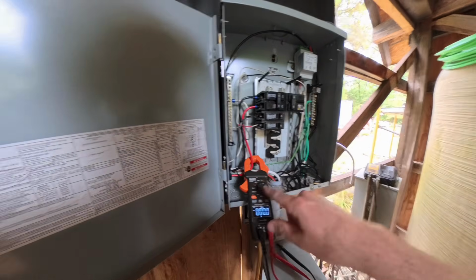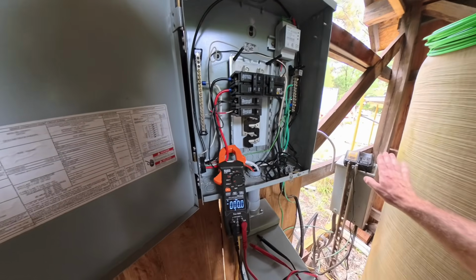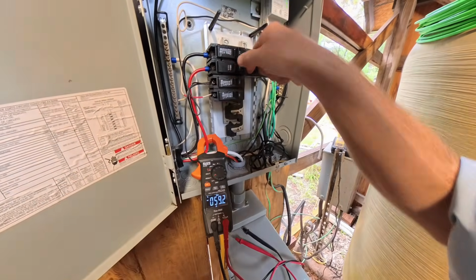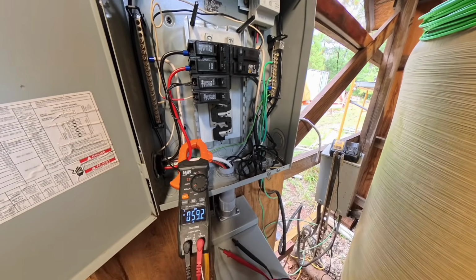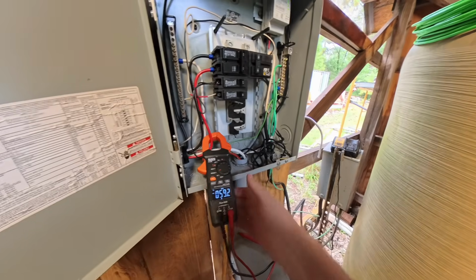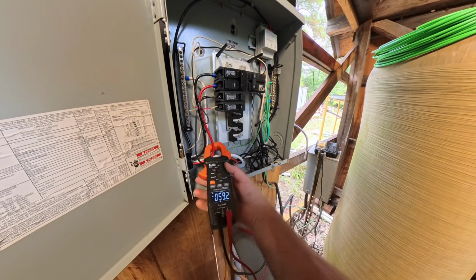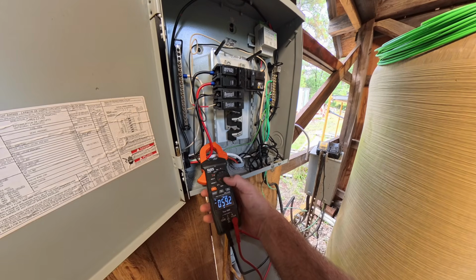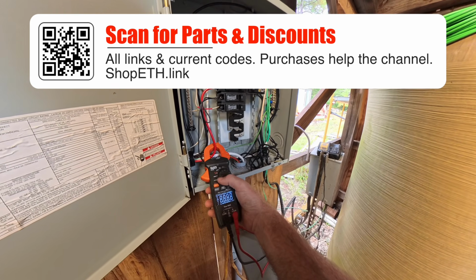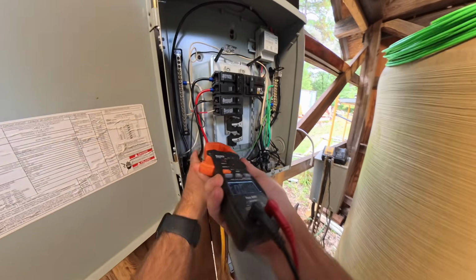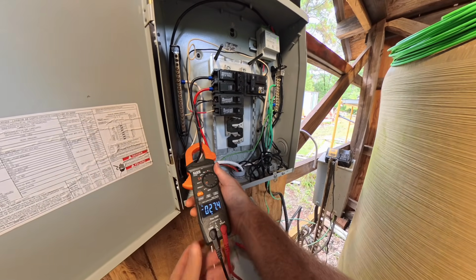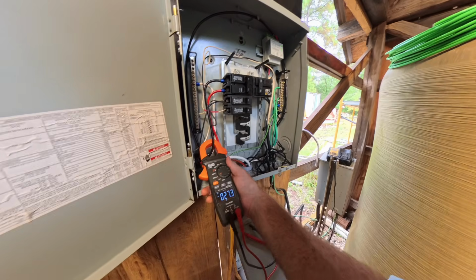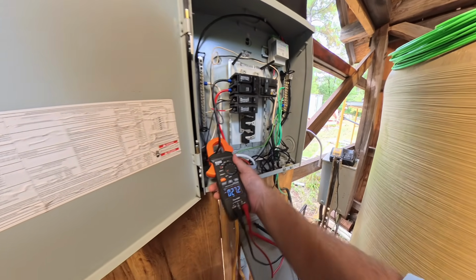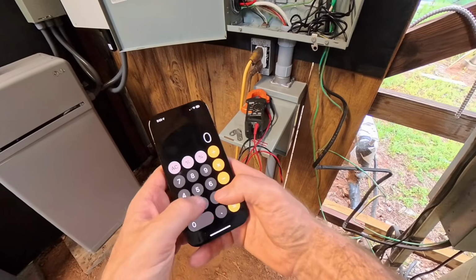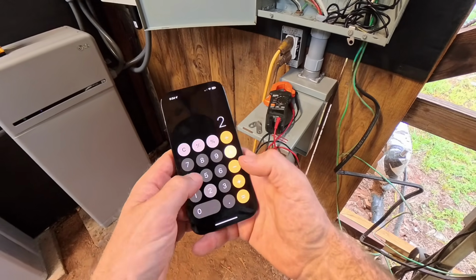I'm going to flip this on so we can get a maximum amperage to see what the initial inrush is for the well pump. 59.2. And continuous, 25. 59.2 with continuous 25, that's on L2. L1 actually has 27, but that's because there's some lights on this and the Starlink Mini.